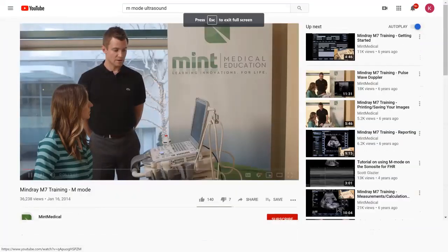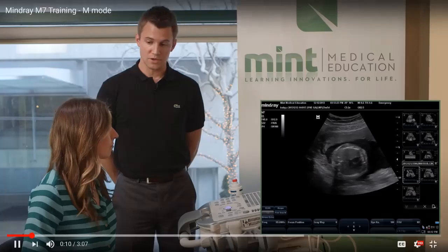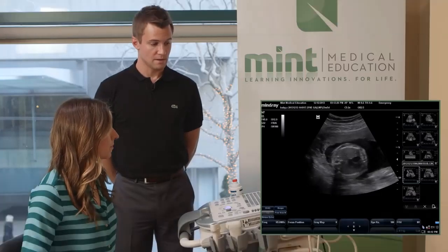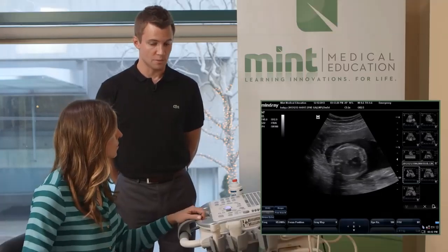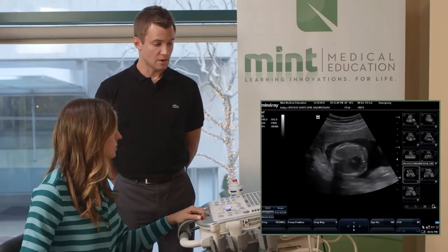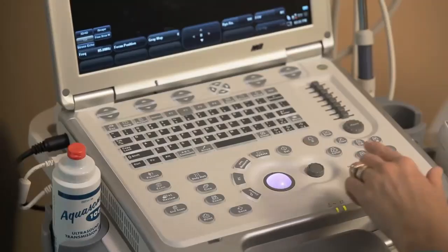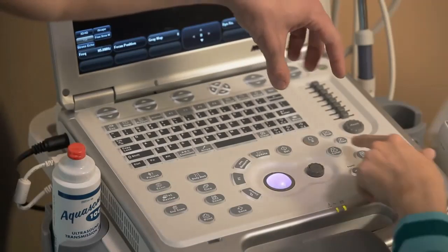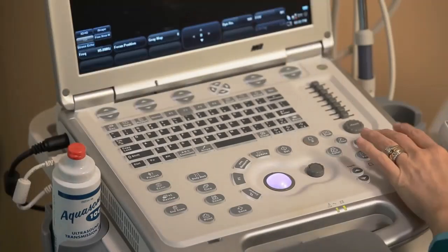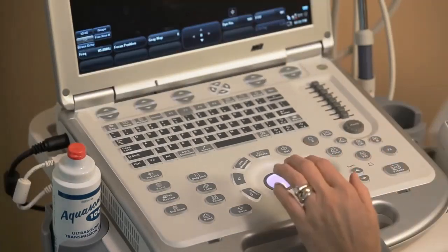Okay, so our next topic is M mode, which is motion mode, and the exam type that we're using here is OB second trimester scanning. Along with your other modes and functions, you have M mode that's over on the far side of the keyboard. And when you hit that once, you get that green line.